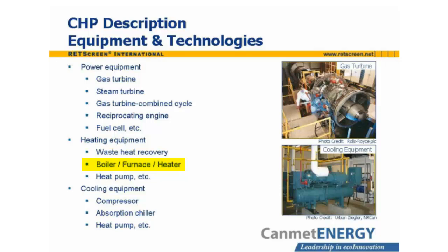When only low temperature heat is available, it can be used to preheat water destined for steam generation. Low temperature heat can be conveniently transported from the plant to loads in streams of hot water. A heat exchanger recovers the waste heat from the power generation equipment. The hot water can be used directly for domestic hot water or space heating, and the temperature can be raised somewhat by a heat pump if necessary. CHP plants will often include dedicated heating systems such as boilers and furnaces to supply heat in combination with, or in addition to, that available from the power plant.